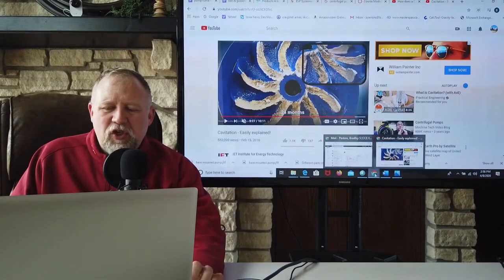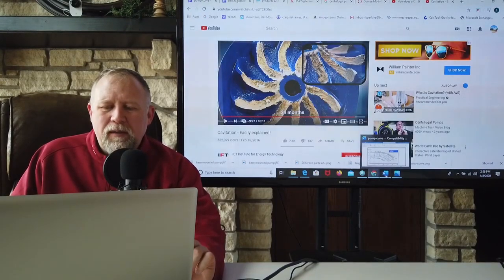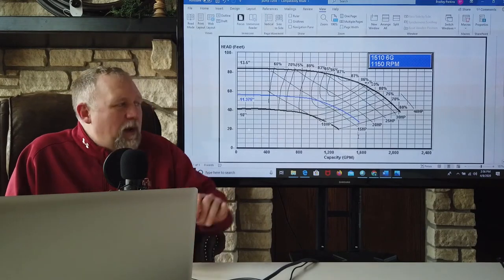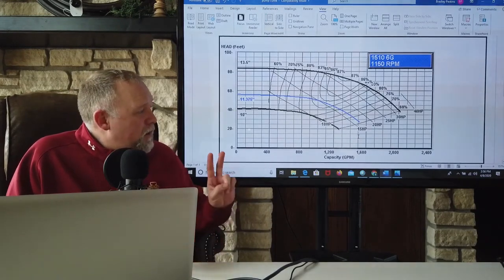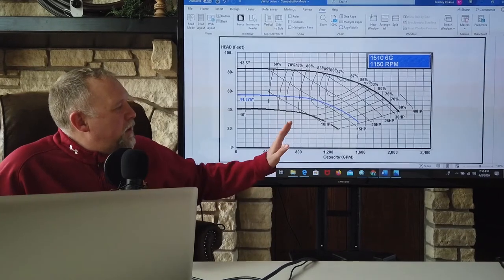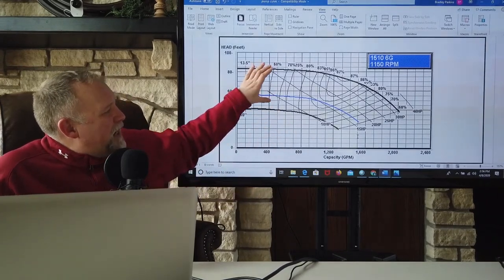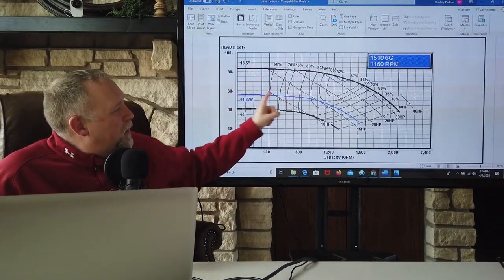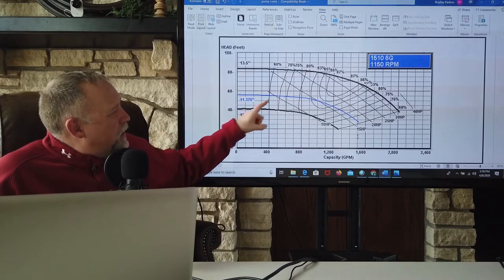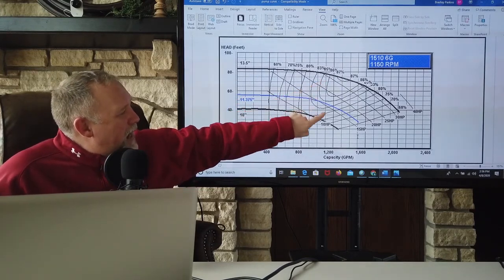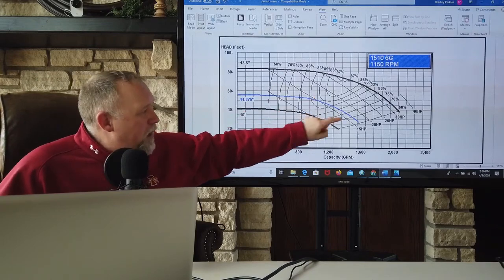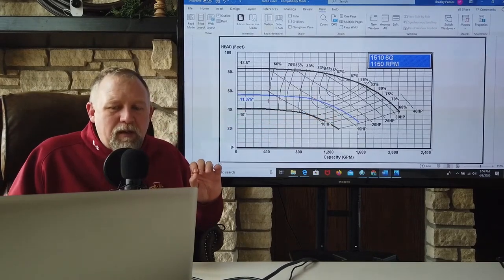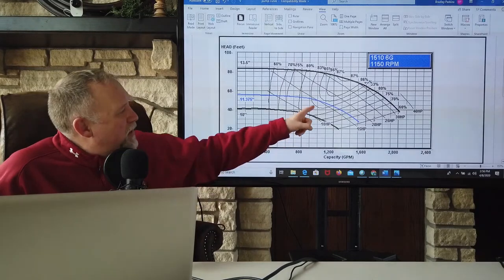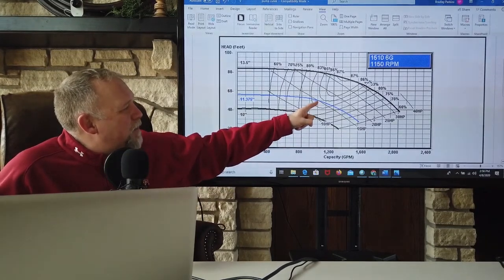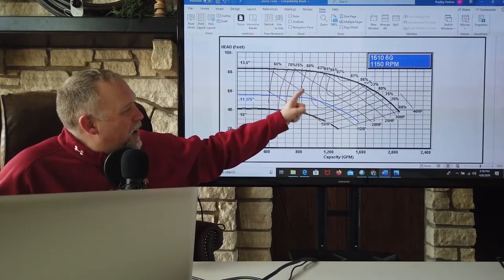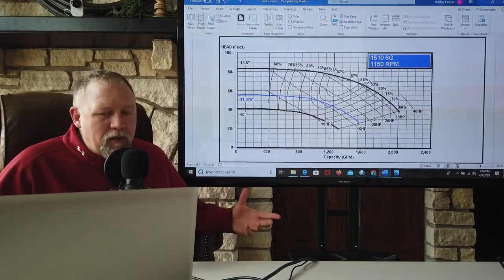So you just have to make sure that, one, you pick the right pump. Two, you know the appropriate combination of impeller size, impeller diameter, speed, and motor draw. To avoid smoking a motor, make sure that you have not selected a motor size that crosses this impeller curve. That would be called an overloading pump curve.